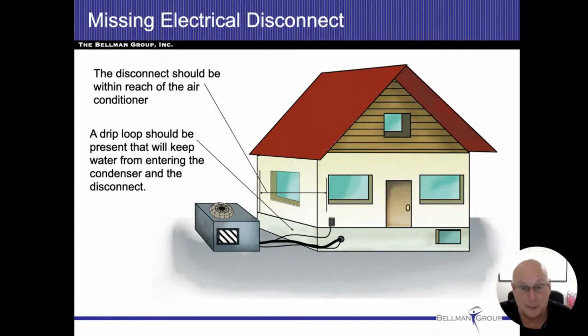So the purpose of this disconnect, it's there to protect the guy that's working on the air conditioning cabinet. If he goes in there, he opens it up, and all of a sudden it starts working, he needs to be able to turn that power off right away. So for me, when I look at these disconnects, if I'm in front of the unit on my knees working, I like to see a disconnect that's within easy reach, just in case the unit does start up.